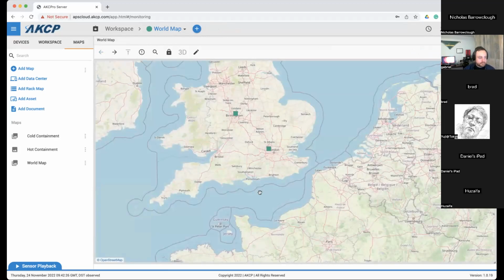What Nick was demonstrating was the heat maps, which is a representation of the instantaneous sensor values that you have in your data center. And as you noticed on the heat map, it only showed the point values of that temperature right where the sensor was. That's different from what the work that Gabriel is doing. He's taking those point sensor values at a specific location and using those values to compute the airflow throughout the data center. So there's two levels of computation.